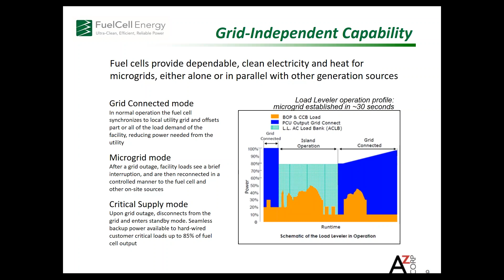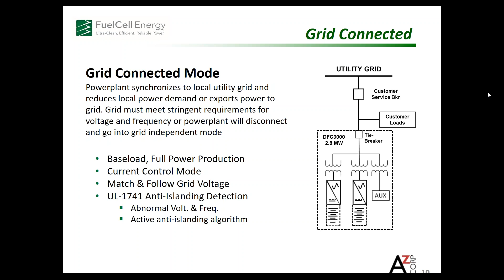Okay, so I have 3 brief slides to address each one of those. I've substantially described them already. I gather that these slides are available to you should you want to look at them offline afterwards. But grid-connected mode, just quickly here, you can see inside the dotted lines and kind of to the top of the box there is a tie breaker. That's the breaker that's opening when the grid is experiencing a difficulty or an outage. And this, of course, is in accordance with UL 1741 and IEEE requirements. We have to disconnect from the grid to avoid energizing and backfeeding a dead grid.